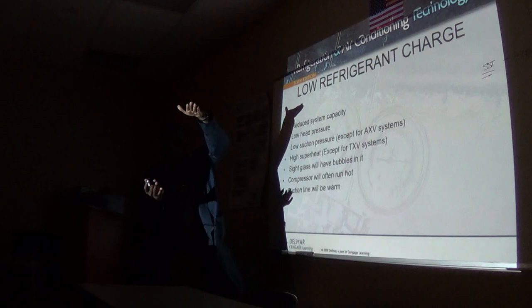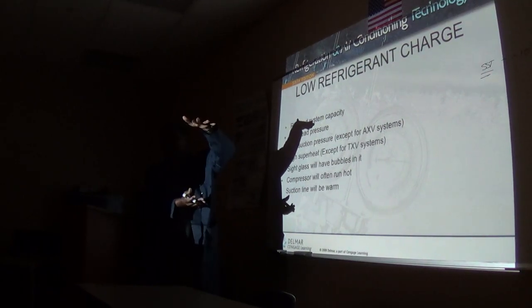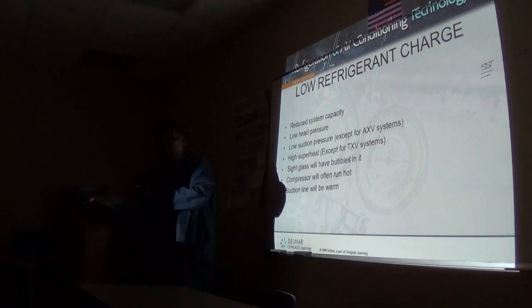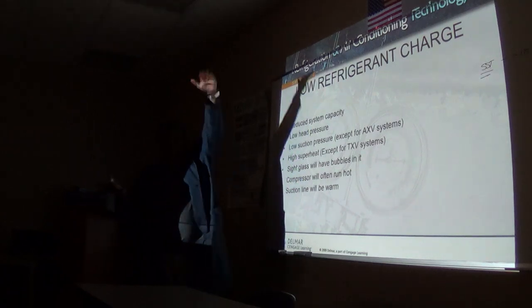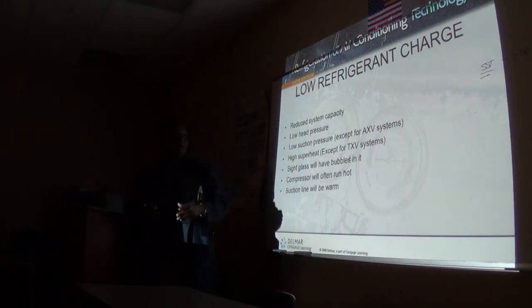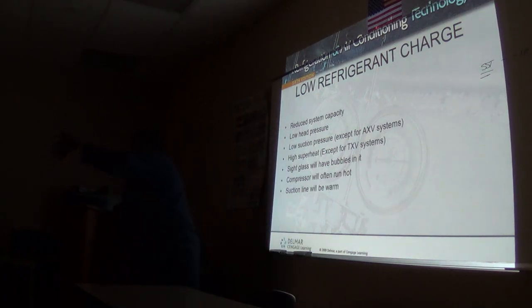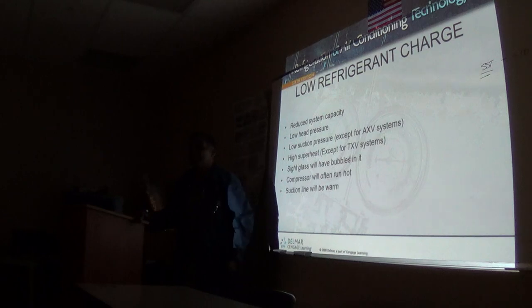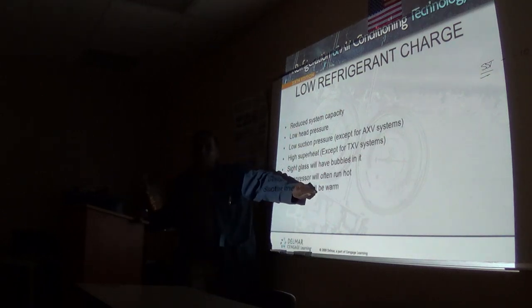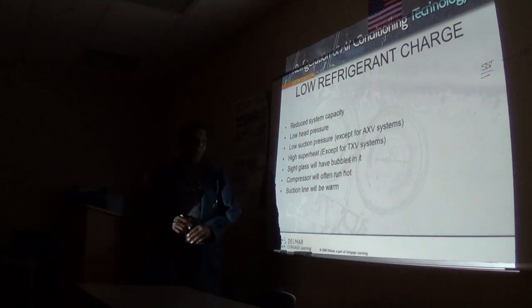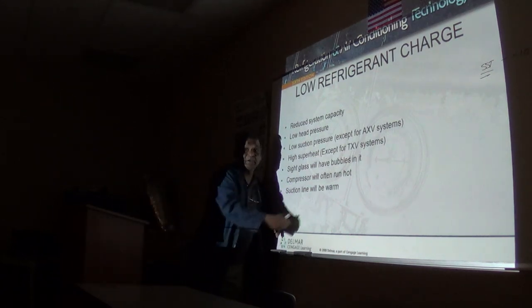But the rest, 90% of the evaporator is absorbing heat. The refrigerant is absorbing that superheat now, and the superheat is sky high. Typically, the maximum allowable superheat going back to a compressor is 20 degrees, so anything above that is going to overheat your compressor. At the compressor? Yes. This was double that, so that's why your compressor is going to overheat.